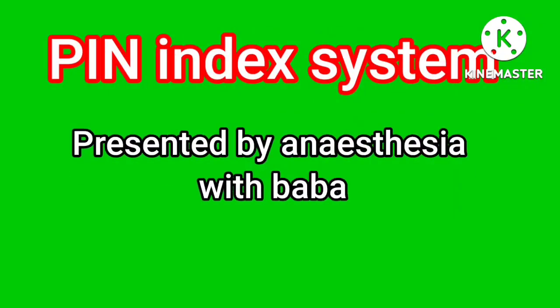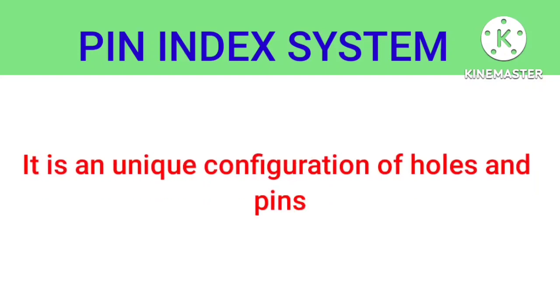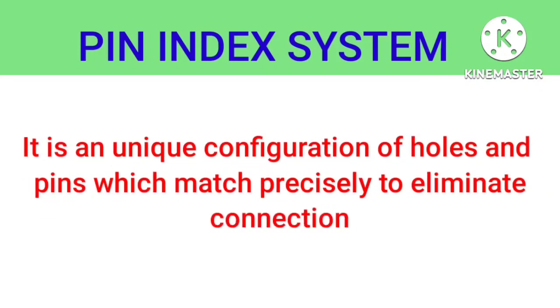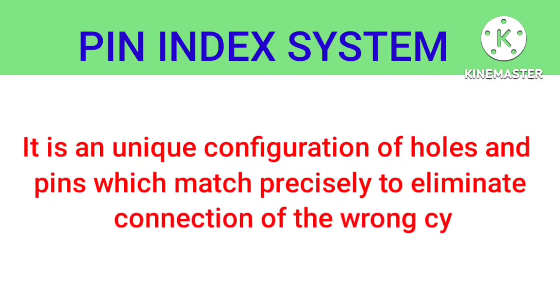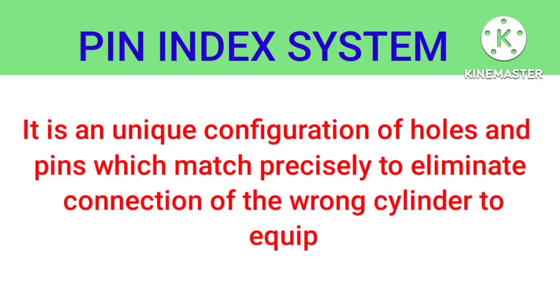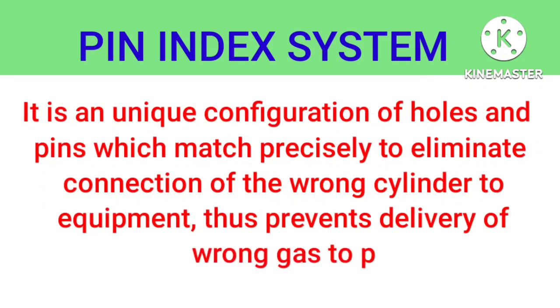Pin Index System, presented by Anesthesia with Babur. The Pin Index System is a unique configuration of holes and pins which match precisely to eliminate connection of the wrong cylinder to equipment, thus preventing delivery of the wrong gas to patients.